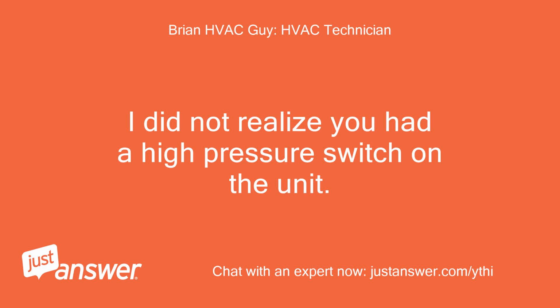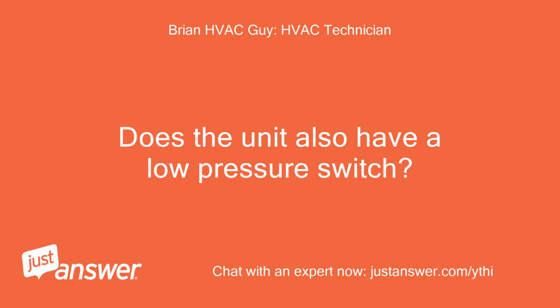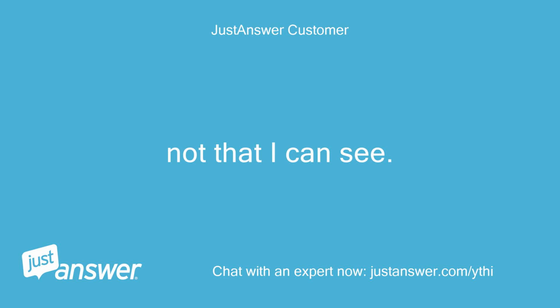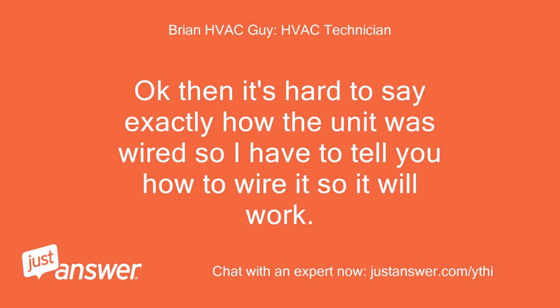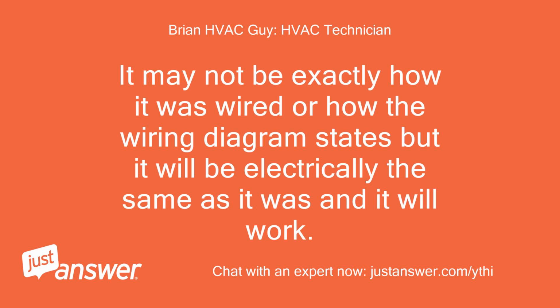I did not realize you had a high pressure switch on the unit. Does the unit also have a low pressure switch? Not that I can see. Okay, then it's hard to say exactly how the unit was wired, so I have to tell you how to wire it so it will work. It may not be exactly how it was wired or how the wiring diagram states, but it will be electrically the same as it was and it will work.